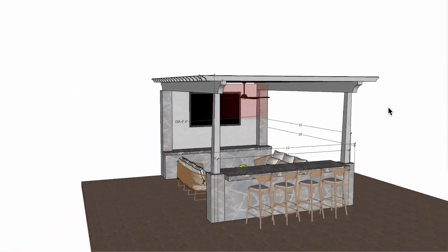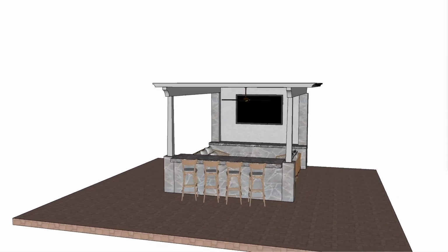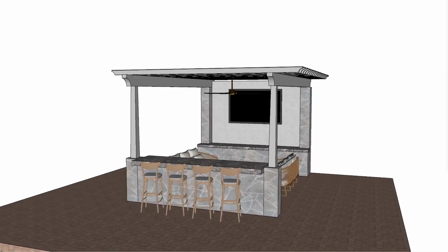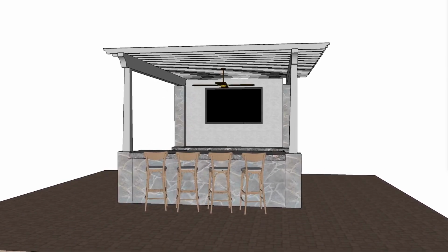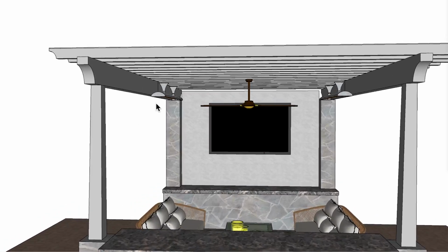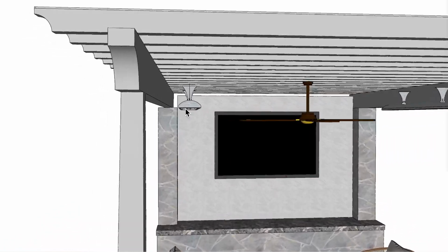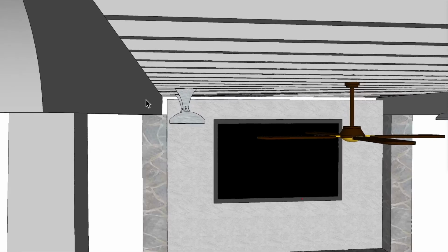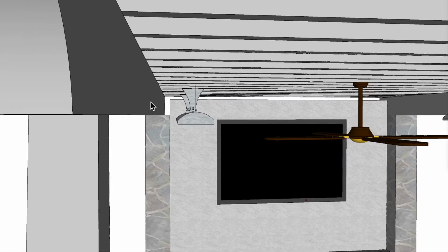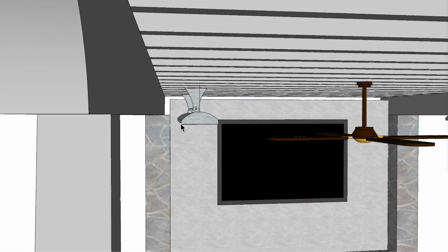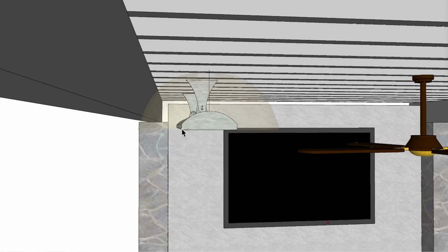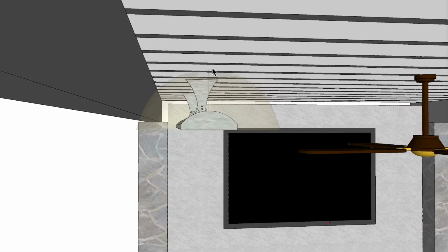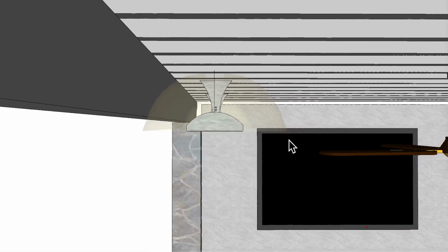So let's go ahead and turn off the dimensions and look at what my recommendations might be. The client did ask for the CD6024s, which I think would be a good option. Now, I've placed these CD6024s so that they are 6 inches away from this beam here to this edge here. So if you looked at the clearances to combustibles on the above side of the heater, you're at 6 inches all the way from the left edge here, all the way up and around, 6 inches to the right side.